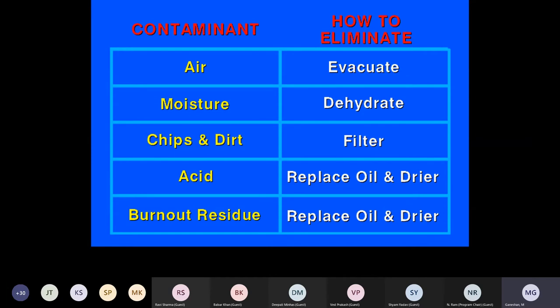So that non-condensable will remain, and around 20% of the condenser will not work as a condenser, because it cannot condense or transfer heat there. That is why we always do a proper vacuum. Why we say do dehydration properly during the initial stage is because any air or nitrogen can damage systems in the long run. Immediately it will not happen, but continuously in the long run.